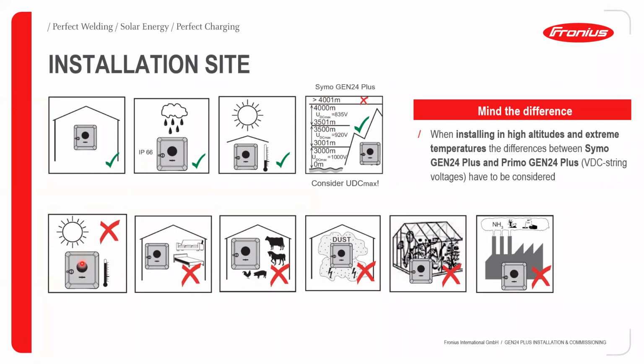Yeah, so installation directly under sunlight is possible, but at some point, if the ambient temperature exceeds 50 degrees Celsius, derating will occur. Derating simply means that instead of overheating or over-laboring the power electronics, the inverter automatically cuts down its power production to a certain level, so as not to overwork the power electronics. That is in the event of the ambient temperature exceeding 50 degrees Celsius. For other products, you have this happening even at 35 degrees Celsius ambient temperature.